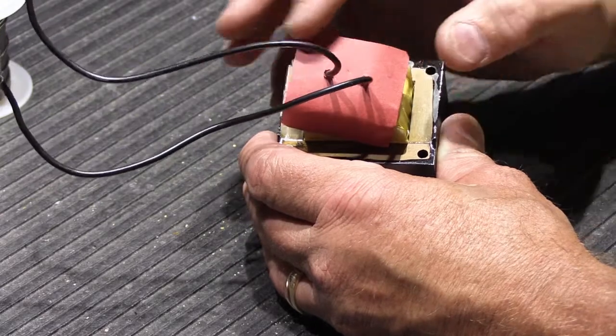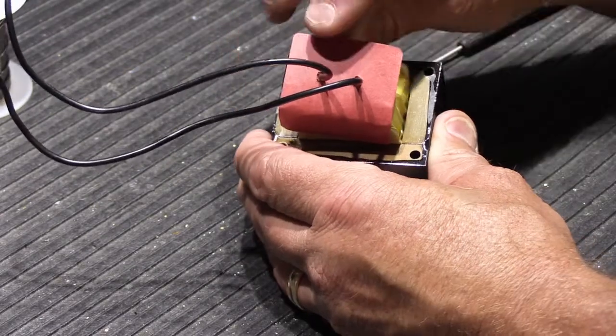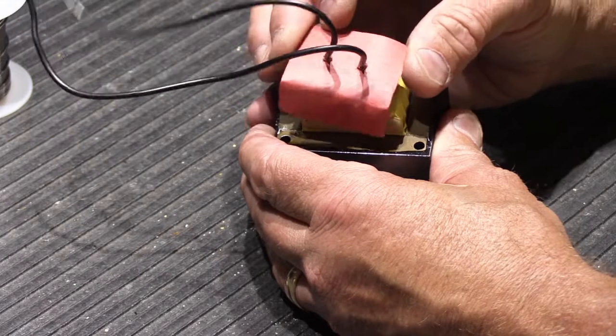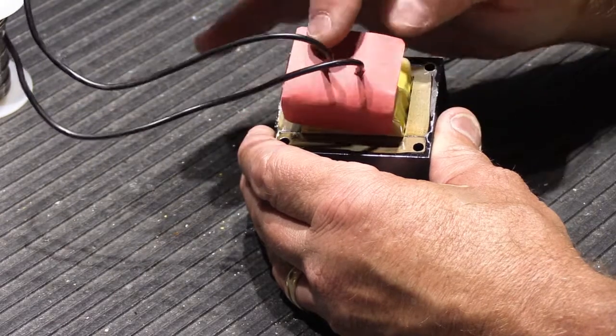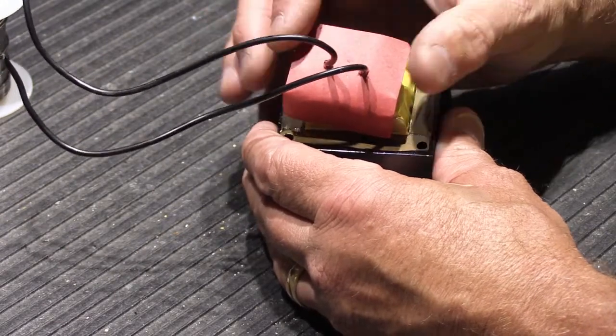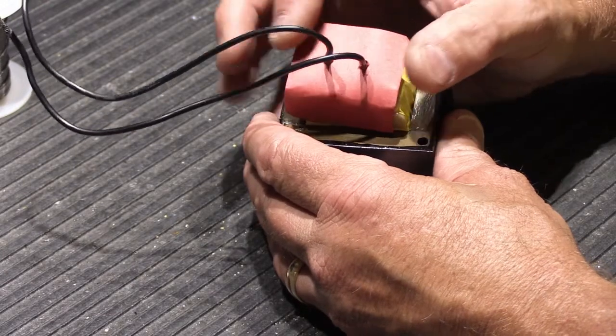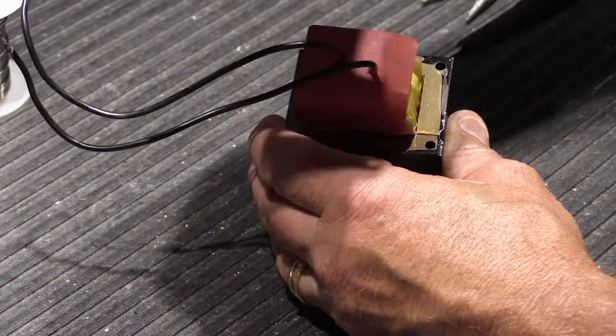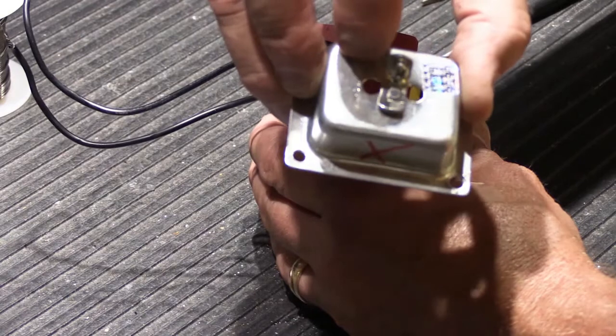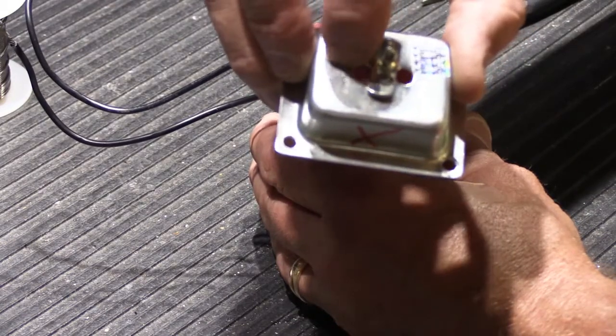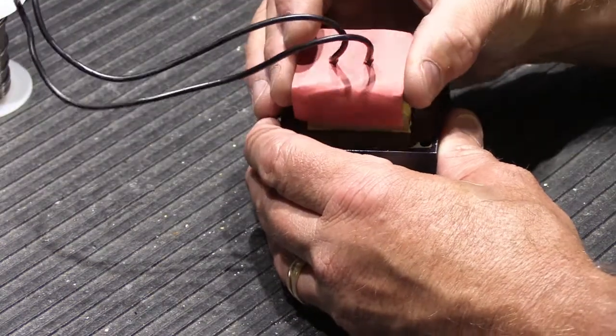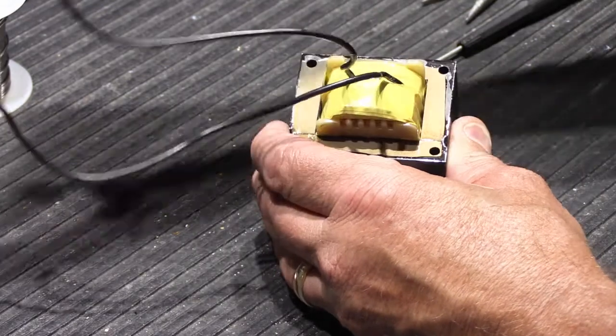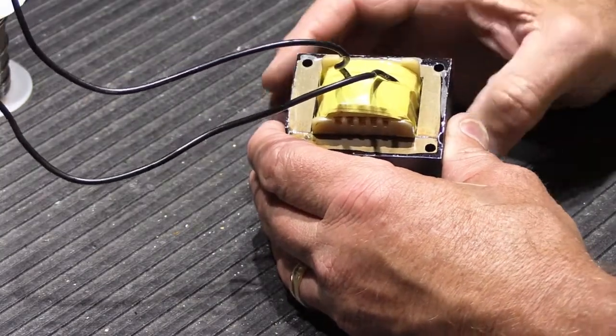On the primary side of the transformer, there's this little piece of red cardboard insulation material that has holes for the wires to go through. The purpose of that is to keep the wires from rubbing on the edges of the round holes in the end cap, so they don't chafe, wear through, and short out. We're just going to take these off the wires to get them out of the way for now, and put them back on later.